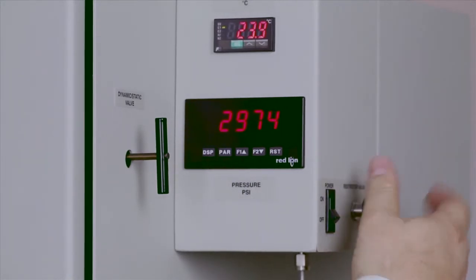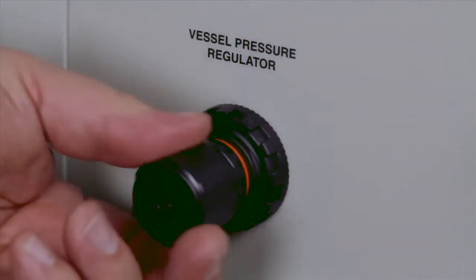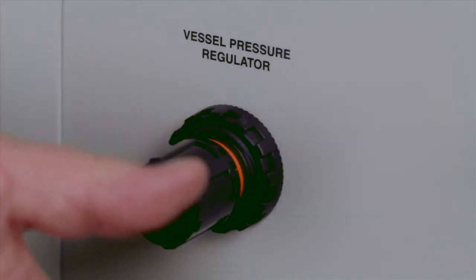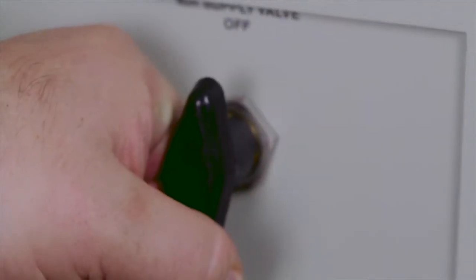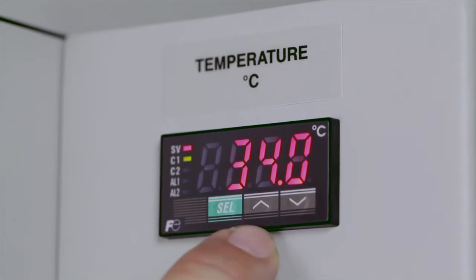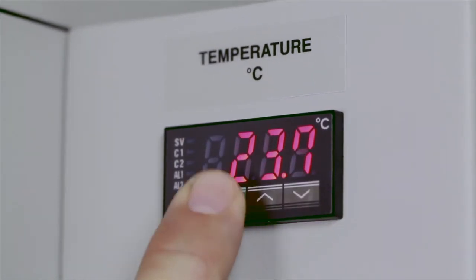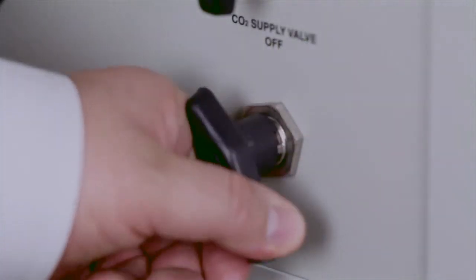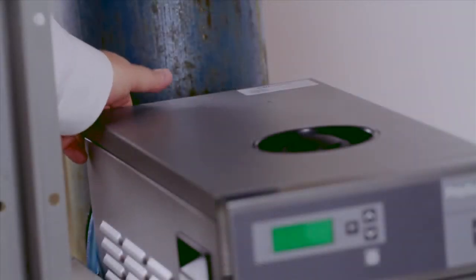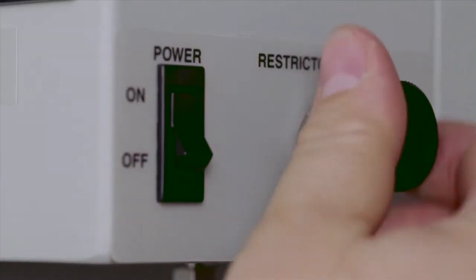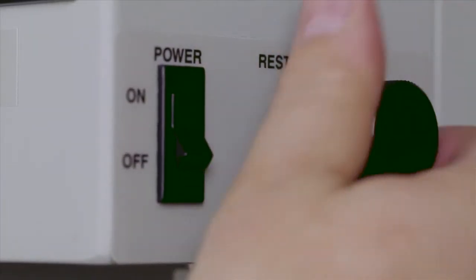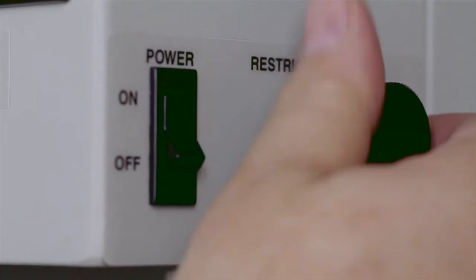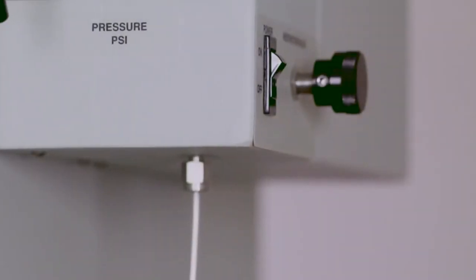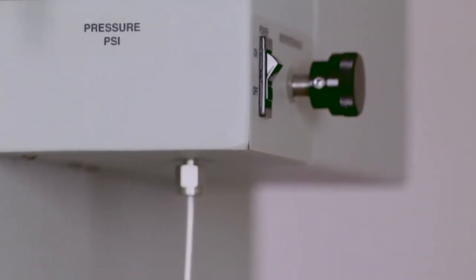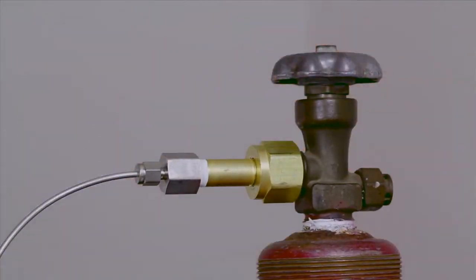At the completion of your extraction, set the pressure to 0 psi by turning the air regulator counterclockwise and turning off the air supply. Set the temperature to a few degrees below ambient. Turn off the CO2 supply and the chiller. Open the static dynamic and the restrictor valves, allowing the vessel to vent completely to 0 psi before removing your sample. When the pressure reaches 0, turn off the SFT-150 and close the valve on the CO2 tank.